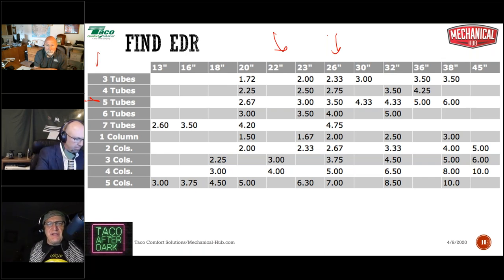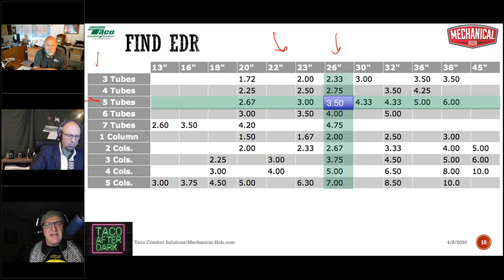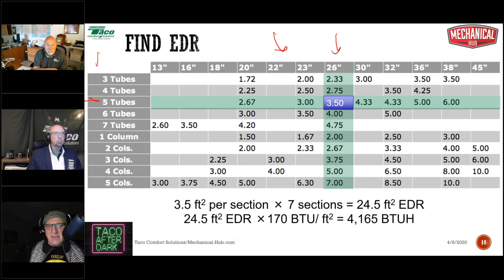So for a five-tube radiator, 26 inches high, we follow the row and the column to where they intersect, and we find that there's 3.5 square feet of radiation area per section. So 3.5 square feet of surface area, if you will, per section of radiator. So 3.5 square feet per section, times seven sections, means the total equivalent direct radiation of that radiator is 24.5 square feet.